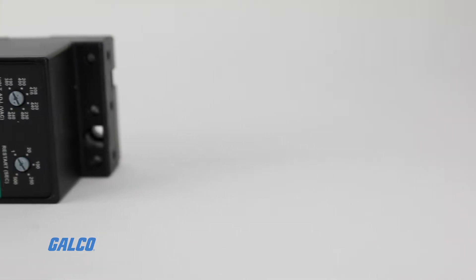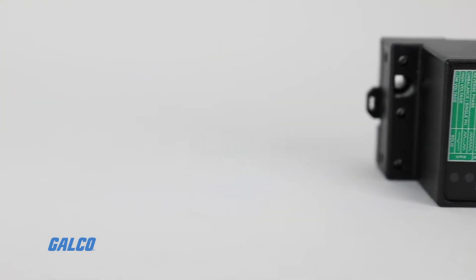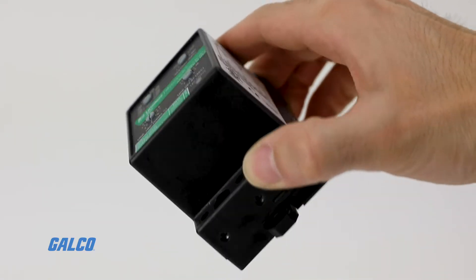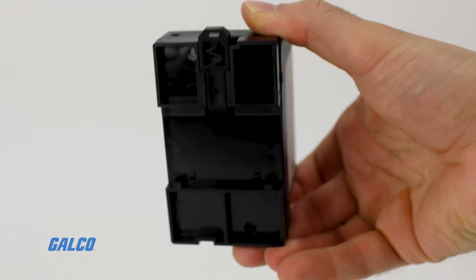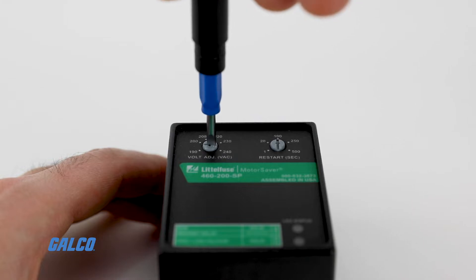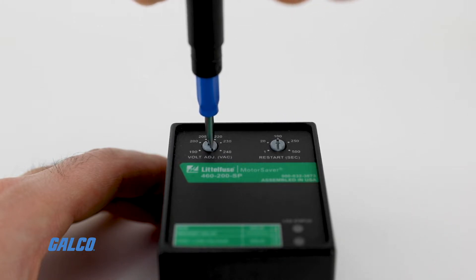460 Relays can provide better reliability during low, high, or unbalanced voltage conditions, as well as phase loss and phase reversal. The relay provides a user-selectable nominal voltage setpoint and automatically senses line voltage for rapid commissioning.